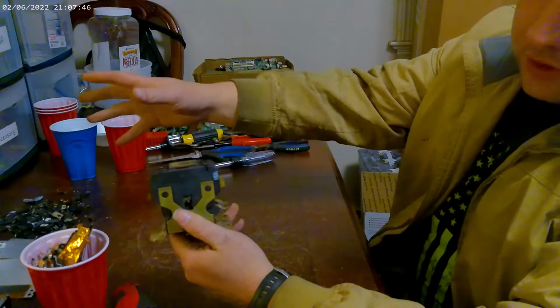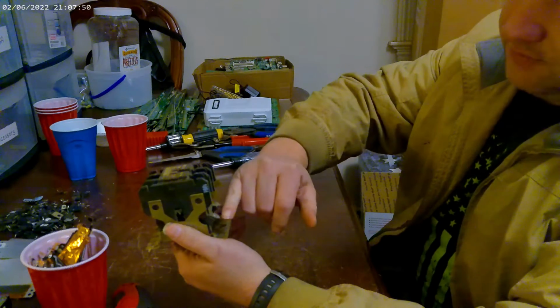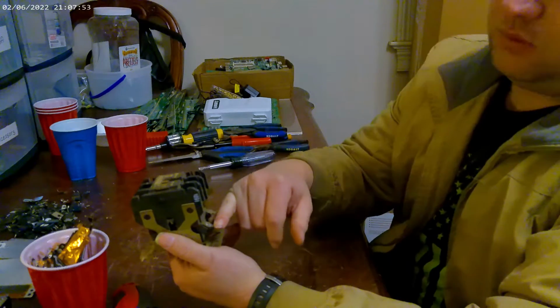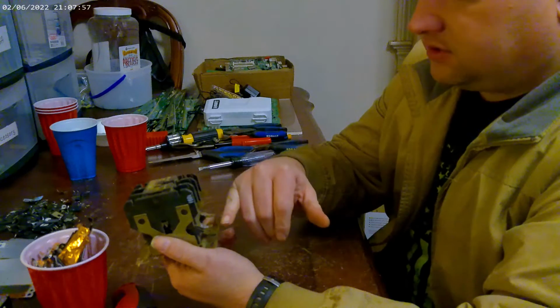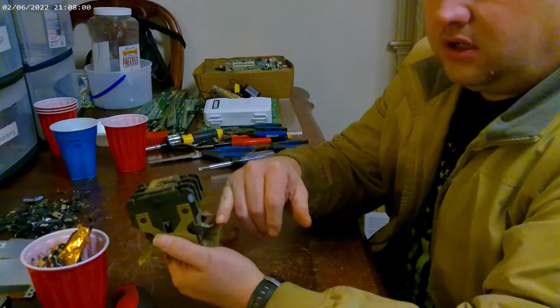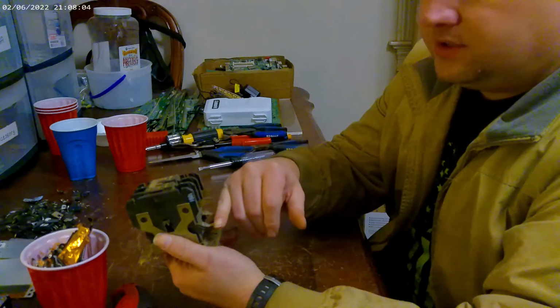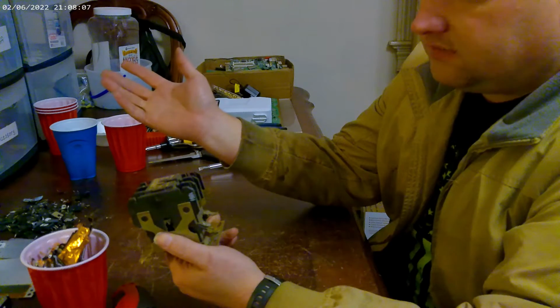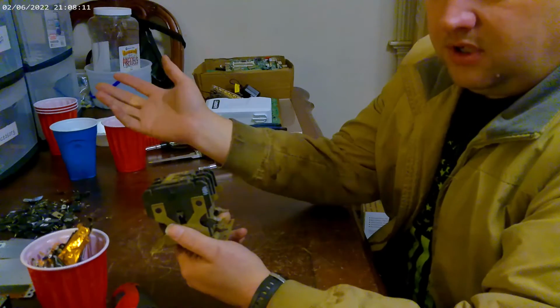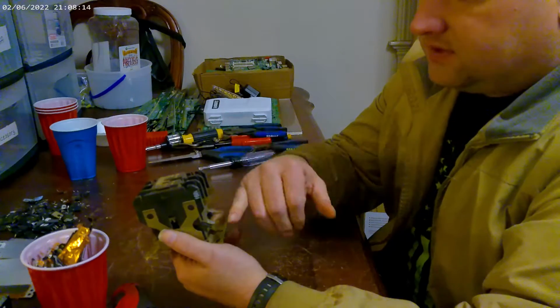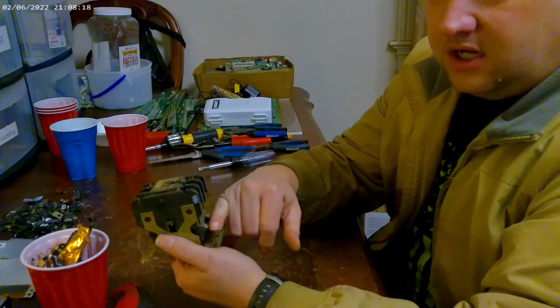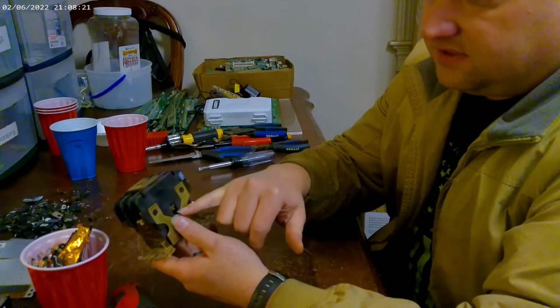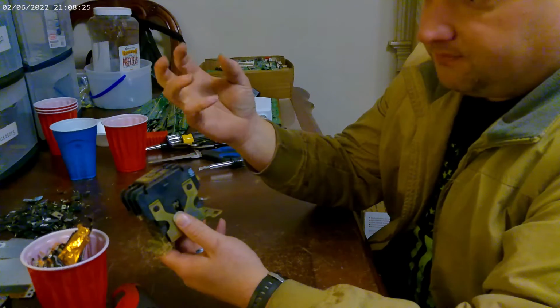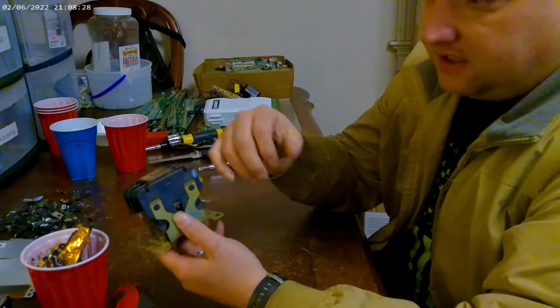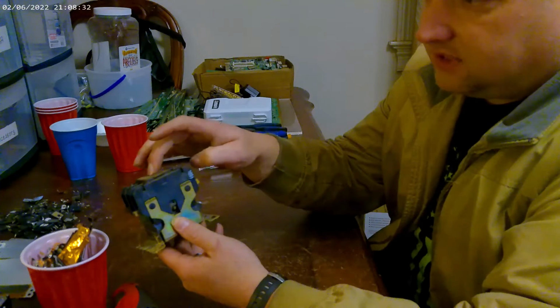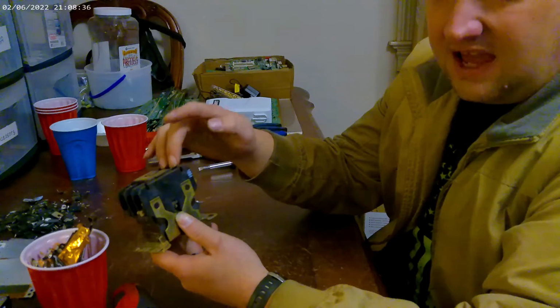So from the small control board, you have 110 or whatever. Just depends on what it's set up for. But your low voltage comes in here, will probably come in off of a switch. It could be a computer relay telling it what to do when, we'll say, the water hits 120 degrees. This contactor is supposed to close and pump and circulate that water to help cool it back down. So that computer relay kicks on right here, energizes the circuit that's inside, makes a magnet effect in here and pulls that contactor down, and that runs the high voltage.